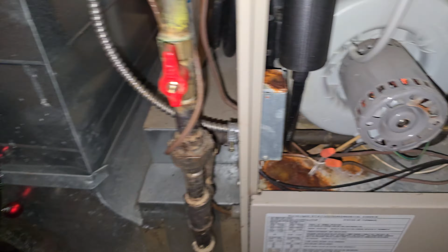Okay, so we're calling for cooling, but it sounds like the motor is humming. So I'm going to see what's going on here. It's a call for cooling, and here is my gas furnace, but the blower motor is stuck. You can hear the noise, it's humming. That means when the blower motor isn't running, it won't be able to take the cooling out from the evaporator coil. So that could be one potential problem. I'm going to dig into it and update you.